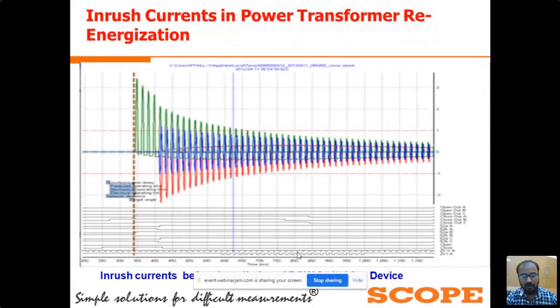So basically, for power transformer application, we are trying to open the power transformer near the voltage peak points. Firstly, we open the R phase and then the Y and B phase. At the time of closing, we use the same strategy: we close the power transformer near the voltage peak point, and by adding some delay, we close the Y and B pole.